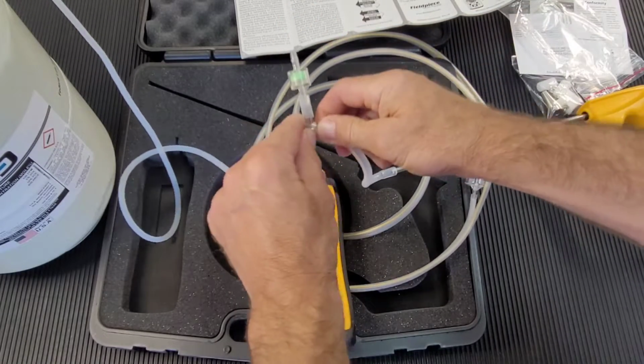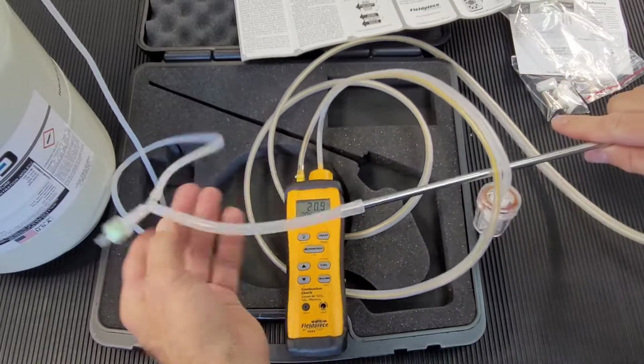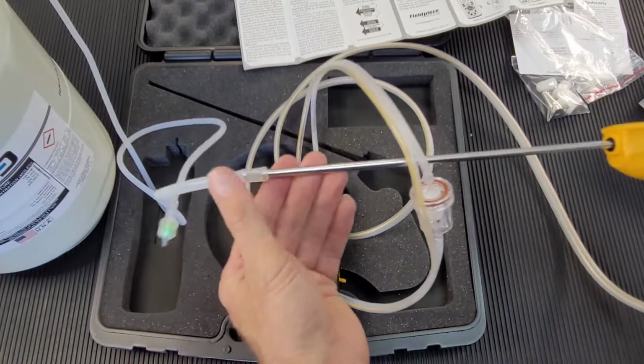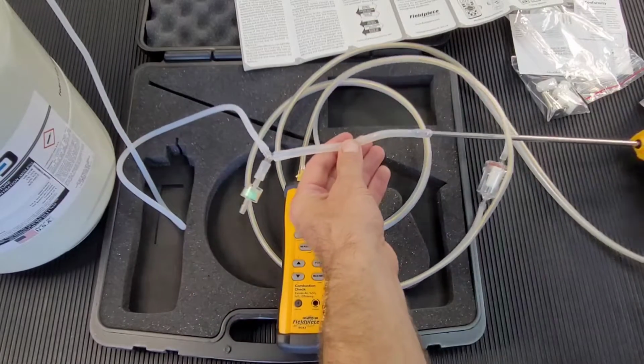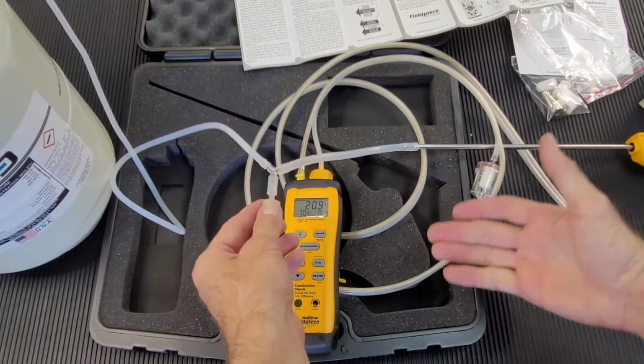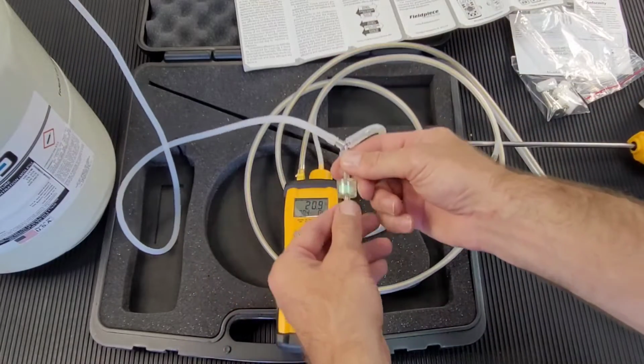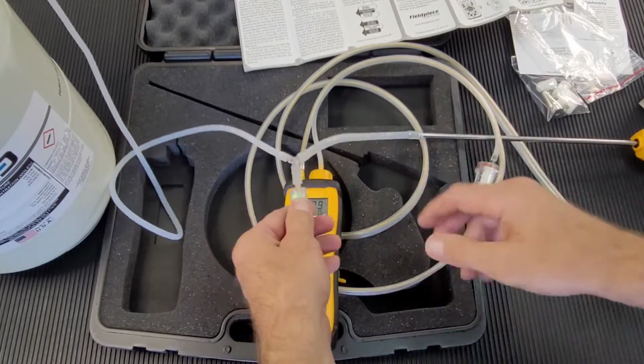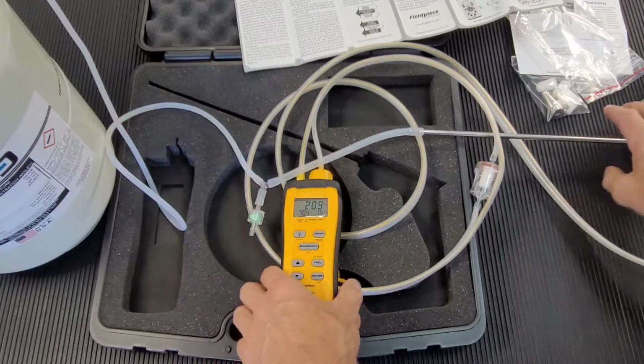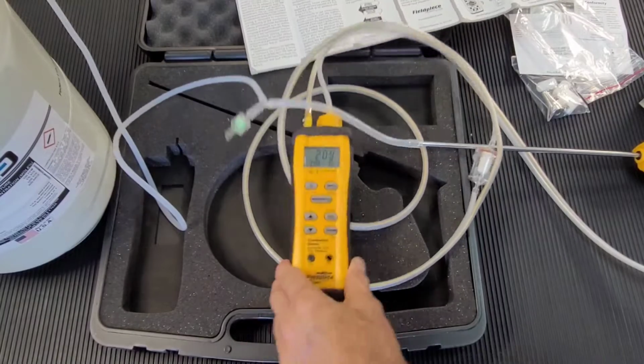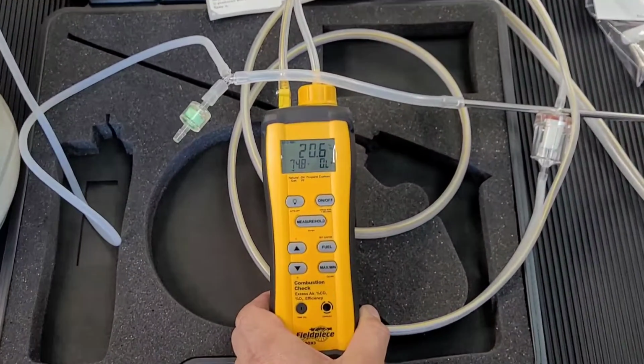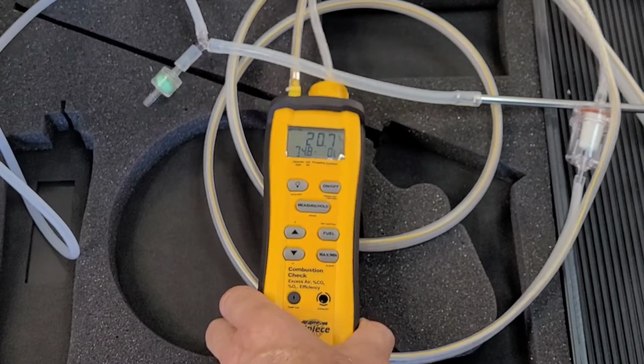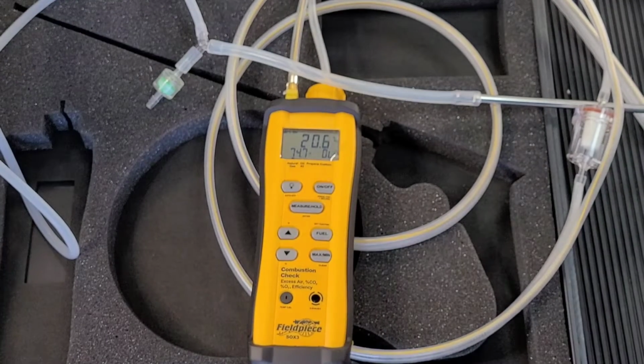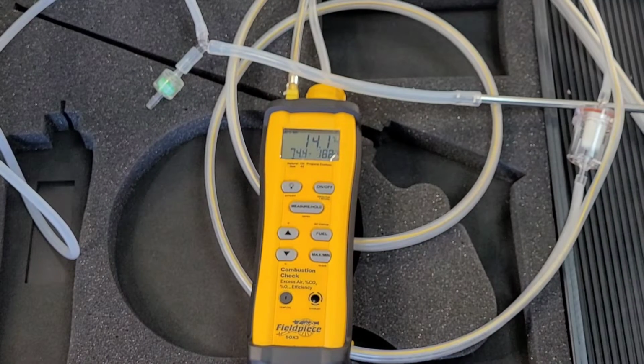So in any situation, with this T-piece arrangement, as you can see, it goes over the end of the nozzle here of the probe, right over here. The right diameter is on. It will be drawing enough air where it doesn't stress the micro pump, and it gives the sensor the flow it needs, reducing the pressure differences that give you a lot of noise. So that's the whole purpose here, folks. Okay, so I'm going to turn on the pump. Let's keep our eyes on the digits here. Every time we turn it on, let it just come to 20.9 and then we're good. Go from there. Okay, let me turn it on right now, 20.3. Okay, folks, so we've got about 0.3 to 0.5 litres per minute running through.